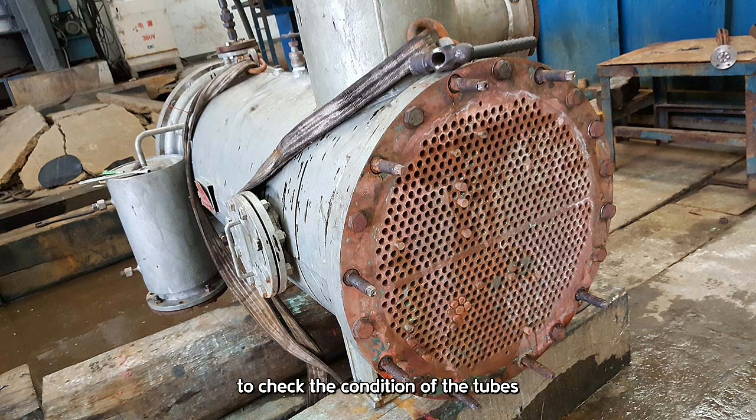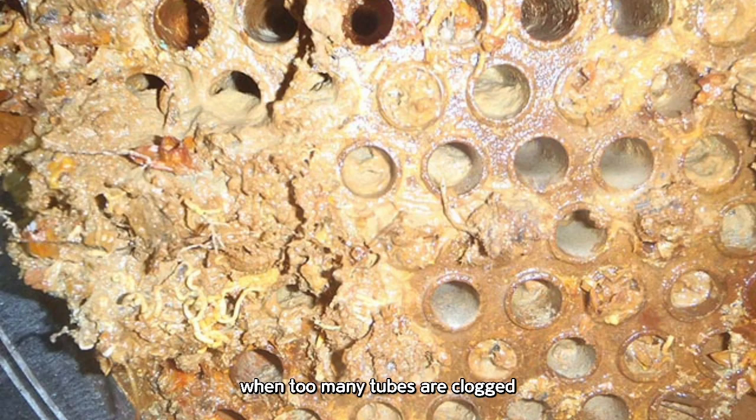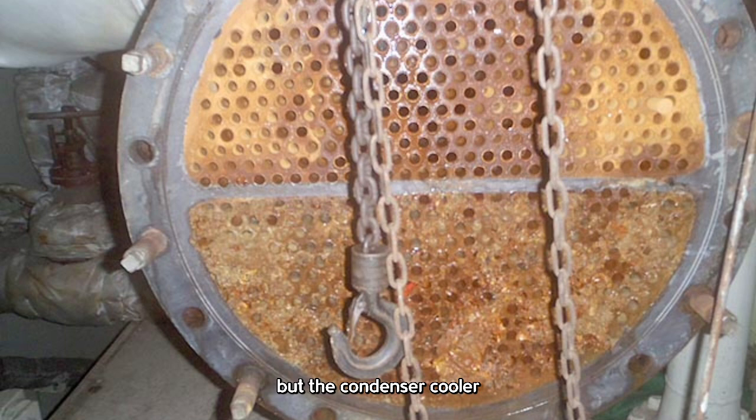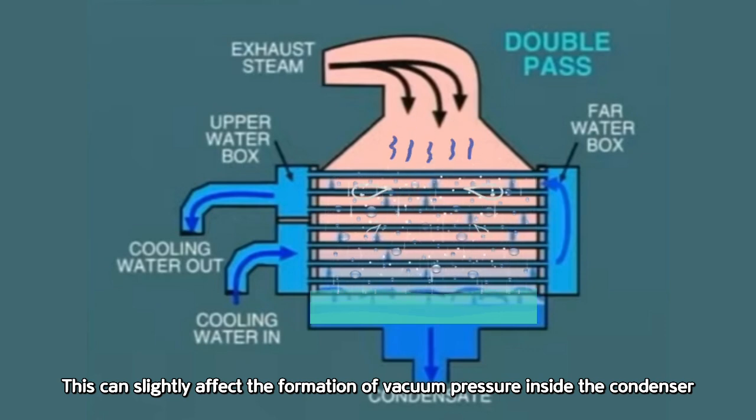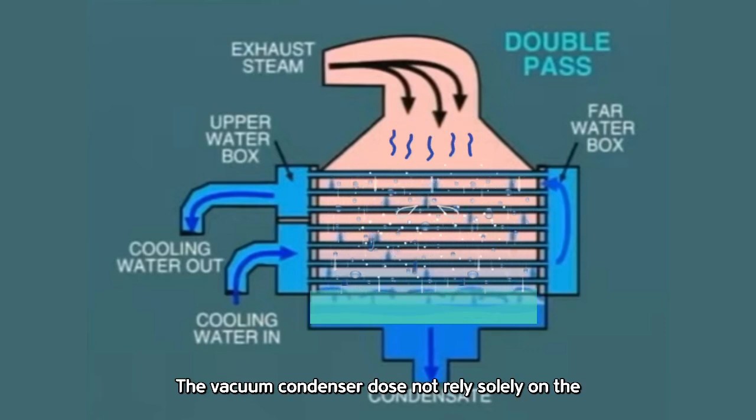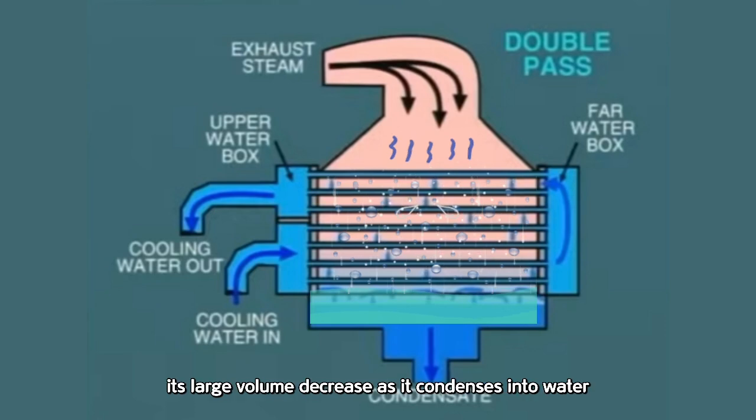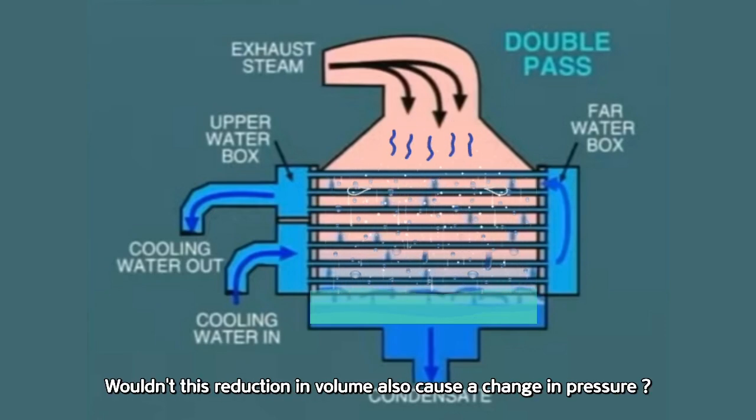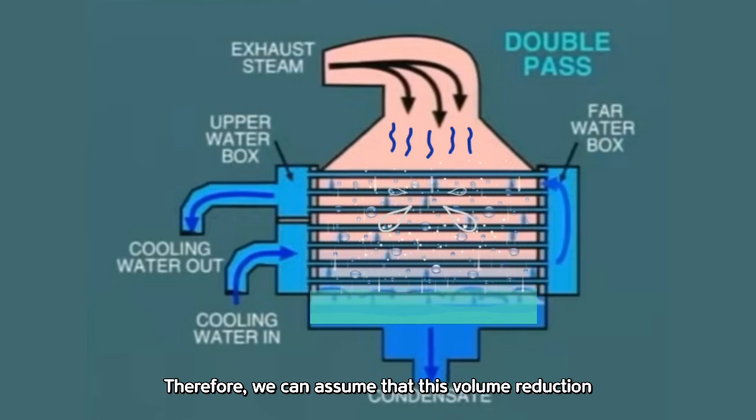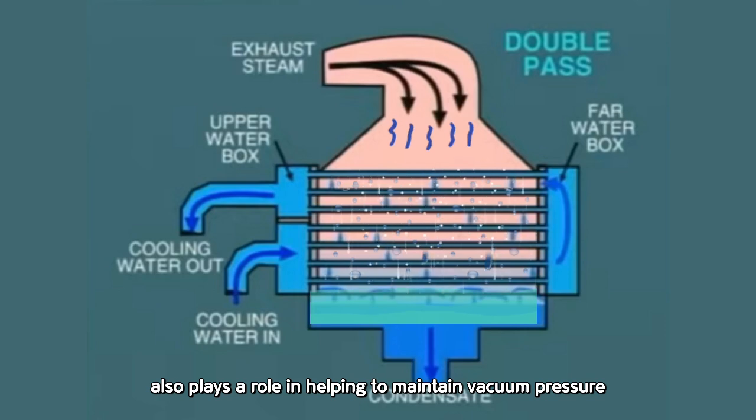Additionally, a pressure test is performed to check the condition of the tubes. If any leaking or damaged tubes are found, but the number is within an acceptable limit, instead of replacing them, they are simply plugged, as shown in the photo, and the condenser is put back into service. When too many tubes are clogged, not only does the cooling efficiency decrease, but the condenser cooler also fails to lower the internal temperature to the desired level. This can slightly affect the formation of vacuum pressure inside the condenser. The vacuum condenser does not rely solely on the performance of the steam ejector to maintain vacuum pressure. When high temperature steam is cooled, its large volume decreases as it condenses into water. Wouldn't this reduction in volume also cause a change in pressure? Therefore, we can assume that this volume reduction also plays a role in helping to maintain vacuum pressure.